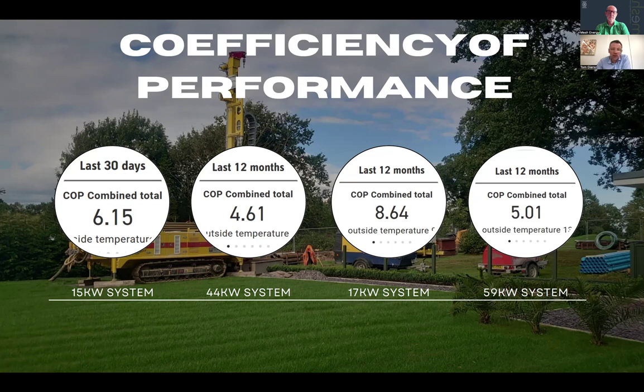Those systems are then cycling, also because the heat pumps are measuring the temperature in the morning. When the system is trying to run, the heat pump says, oh, it's 15 degrees or 10 degrees outside, I will only generate 35. The house has cooled down overnight. Now the 35 degrees going into underfloor heating takes a long time to bring the house up to temperature, and much more energy than if you are just trickling the heat all the time, 24 hours a day. So that's how we found out they work better, especially in older properties that are leaky, with older windows, draftier properties. It's definitely much better to run like that.